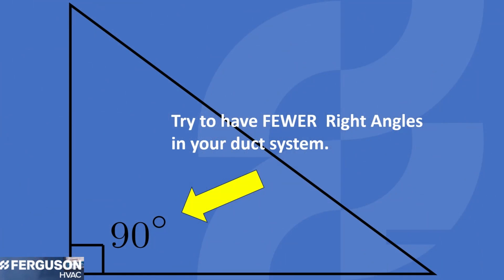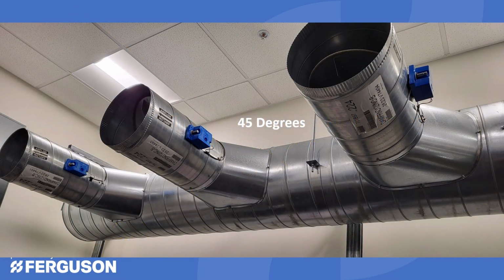When designing ductwork, try to have fewer right angles in your duct system. Let me show you why. When designing ductwork, you want to direct the airflow where you want it to go. Air is stupid, and when it's going in a straight line, that's all it knows. And when you have a 90-degree angle that the airflow hits up against, it's going to bounce off of that. It's not going to go around the corner like you think it will.